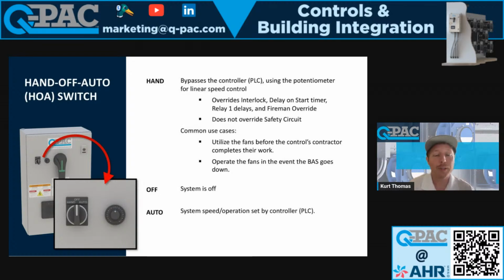Hand mode, I think, is a really great design and a great feature of our control panel. If you are in a critical application, you're in a hospital and you're like, I can never be down. If the BACnet system goes down, or if my BAS goes down, I need a way to run the fans. Hand mode is that option. You can literally take our PLC, hit it with a hammer, pull it out of our control panel, and if you switch it to hand mode and turn that potentiometer, your fans are still going to run. So it is a hard bypass.